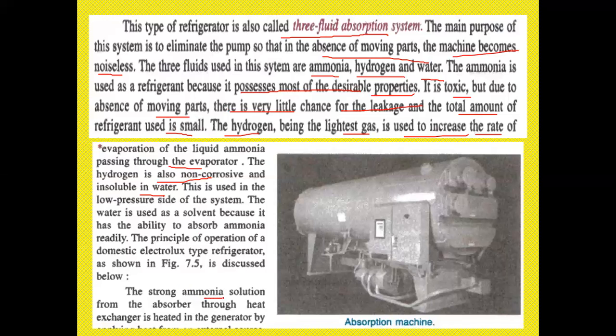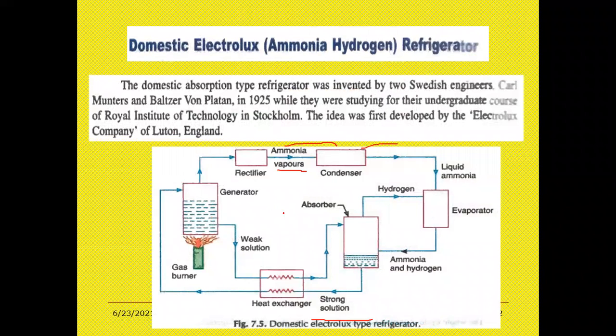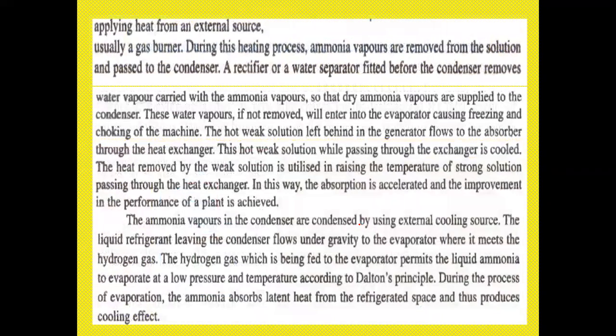The strong ammonia solution from the absorber through the heat exchanger is heated in the generator, right? So from the absorber it is taken to the heat exchanger. Next, heat is applied from an external source, usually a gas burner. During this process, the ammonia vapors are removed from the solution and pass into the condenser. A rectifier or a water separator fitted before the condenser removes the water vapor carried with the ammonia vapors.